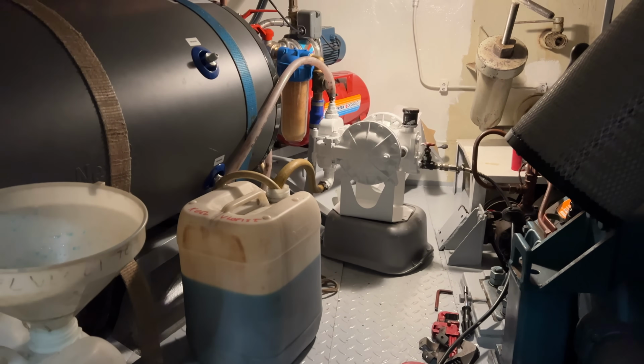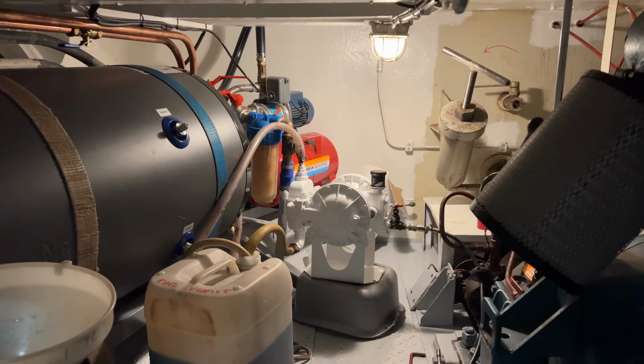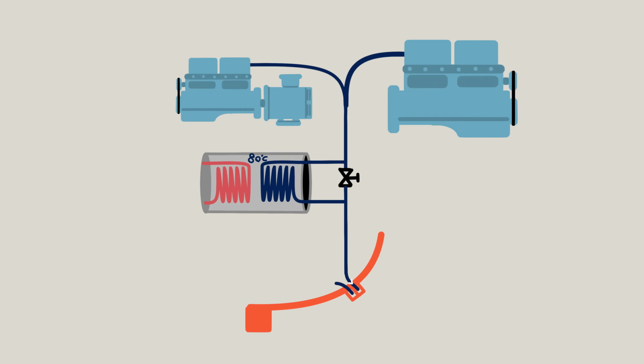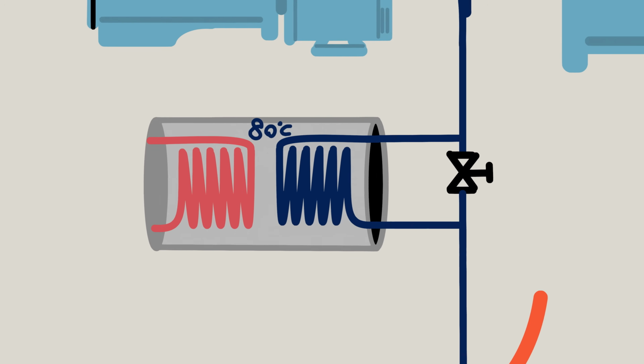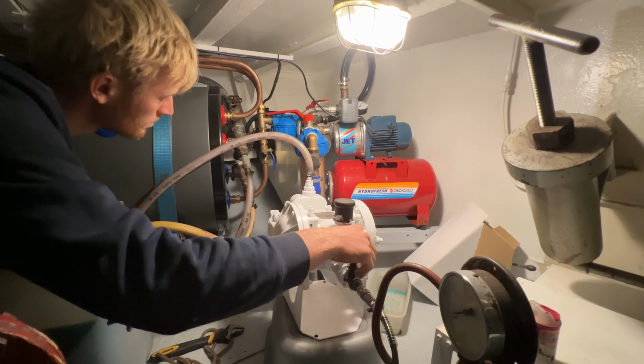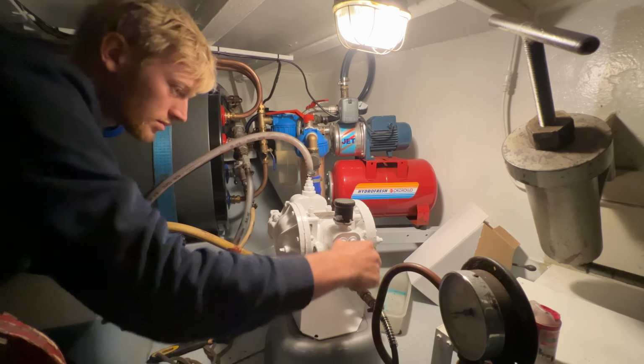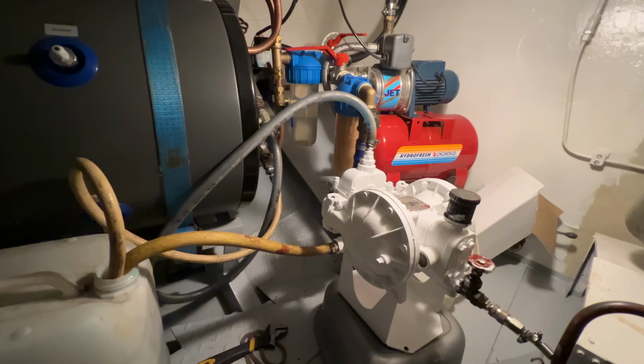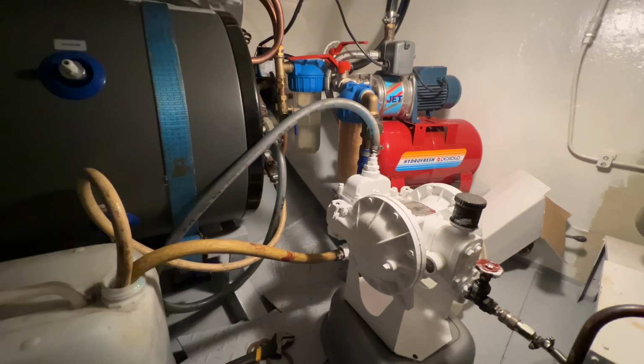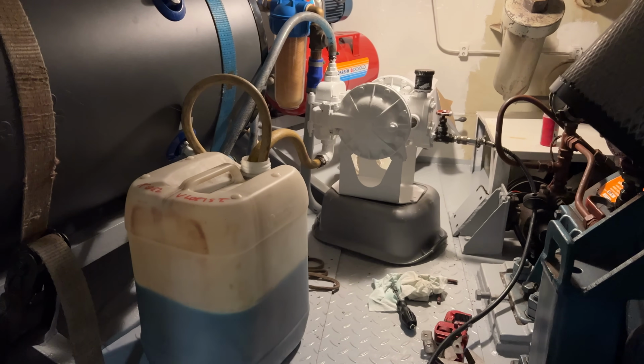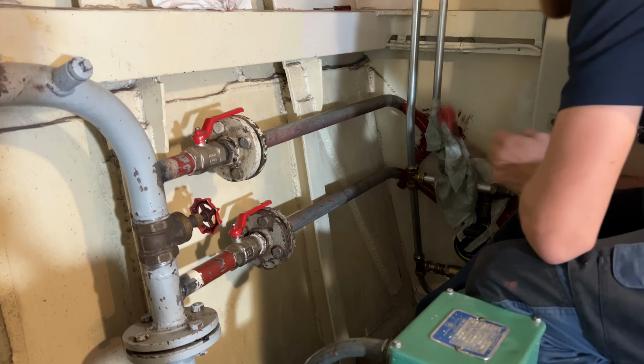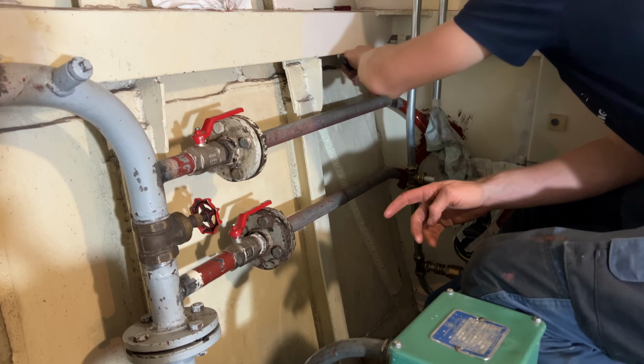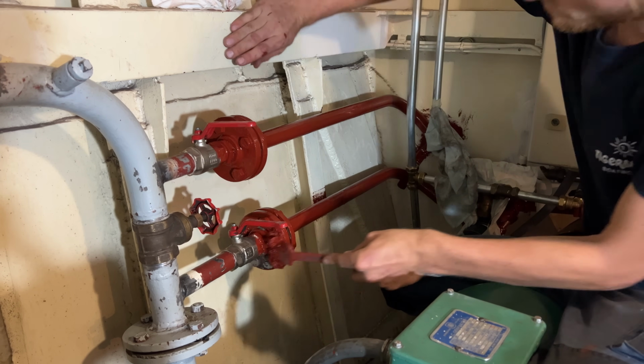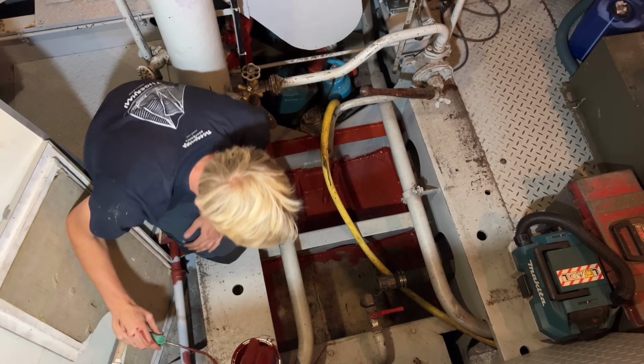After installing everything back, I opened all the valves to fill up the system and tried to let gravity push all the air out of the coil. The problem with a horizontal heat exchanger coil is that there is an air pocket in every loop, and getting those air pockets flushed through takes quite some force, more than just gravity. So I got out the air driven pump and flushed the coil a couple of times to make sure that all the air was out. Of course, all those freshly reused pipes need some paint. And the rest of the engine room should get some as well.